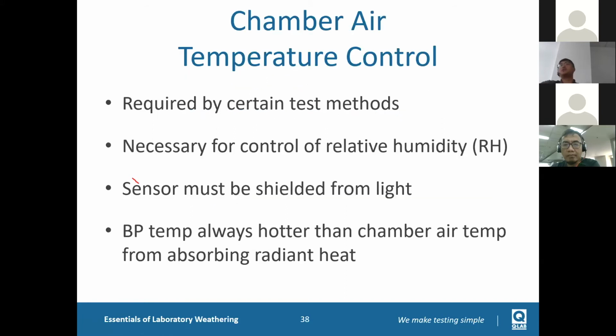Temperature and air temperature control in Xenon Arc chamber: in XE2 and XE3, we have the ability to control the air temperature. In some test methods, in XE1, we can pick BP control, black panel temperature control, or chamber air temperature control. We only pick one in our desktop model XE1, but in XE2 and XE3, we can control both.